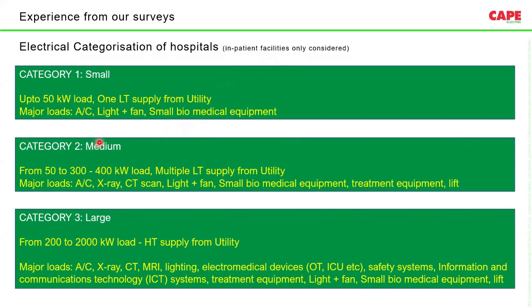The next level is the medium-sized hospitals, where the connected load is 50 to about 300, 400 kilowatts. Here the problem is, instead of going for a high voltage supply, most often for each building or each part of a building, multiple LT, low tension, supplies are taken from the utility. Once multiple supplies are taken, sometimes the wiring practices are not followed properly. In these hospitals, the majority of the load is air conditioners, then X-ray machine, CT scan, light fittings and fans, small biomedical equipment, and so on. Then we have the large category of hospitals where HT, high voltage, supply is available, with proper transformers and all.